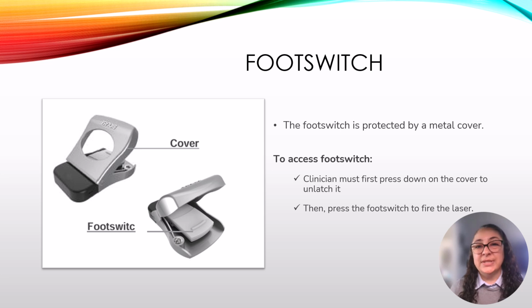The foot switch is protected by a metal cover, therefore to access the foot switch you must press down on the cover to unlatch it, then press the foot switch to activate the laser. If you do not press the foot switch completely down, an error code will be displayed and you will be required to reset the settings through the control button.